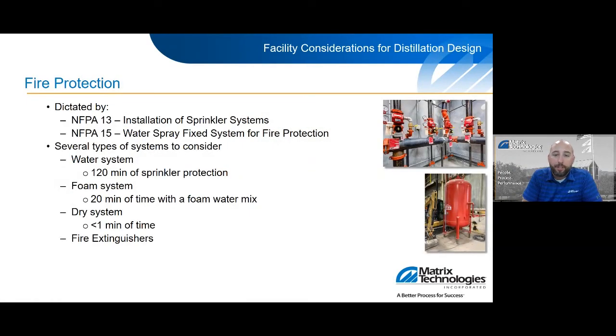Switching on to fire suppression. So fire suppression requirements are often dictated by NFPA, your local fire code, your insurance company, or a combination of all the above. There's several types of fire suppression systems to consider. First one being the water system, pretty traditional style of suppression. This basically is a wet system that's in your facility and requires a demand of up to 120 minutes of sprinkler water in the event of a fire. It's a cheaper style of installation, but will have an effect on your drainage and containment, which we'll touch on in a little bit.